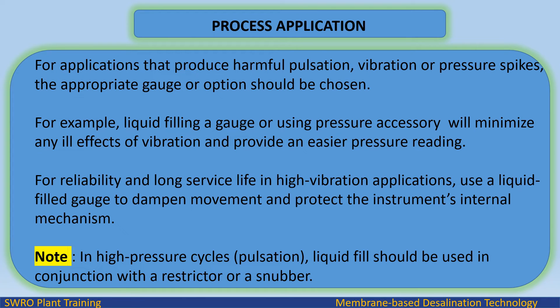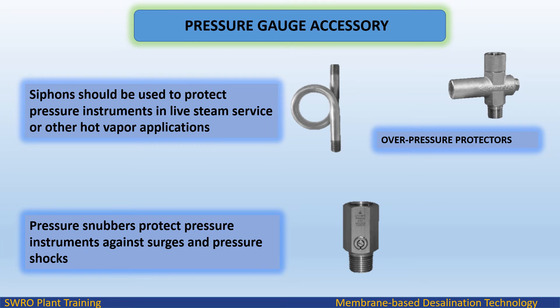Process application: For applications that produce harmful pulsation, vibration, or pressure spikes, the appropriate gauge or option should be chosen. Liquid filling a gauge or using a pressure accessory minimizes ill effects of vibration and provides easier pressure reading. For reliability and long service life in high vibration applications, use a liquid filled gauge to dampen movement and protect the instrument's internal mechanism. Siphons should be used for live steam or hot vapor applications. Over-pressure protectors protect the gauge against exceeding process pressure, and pressure snubbers protect against surges and pressure shocks.